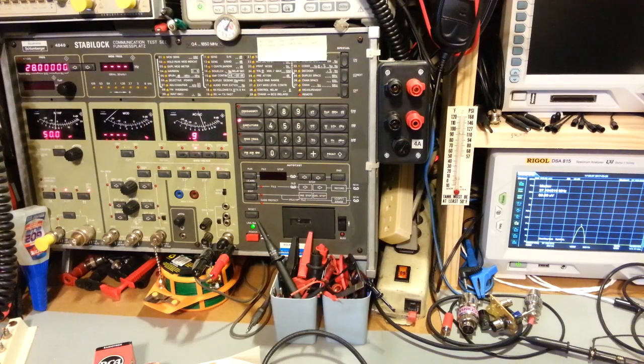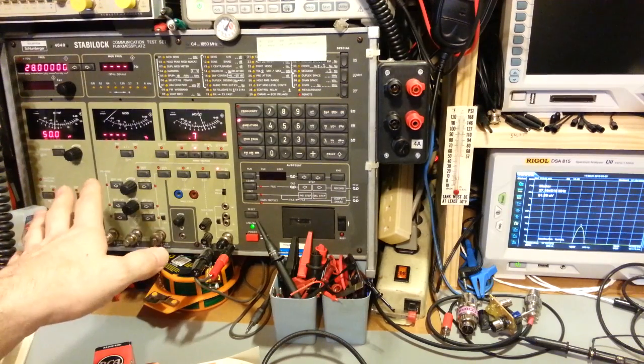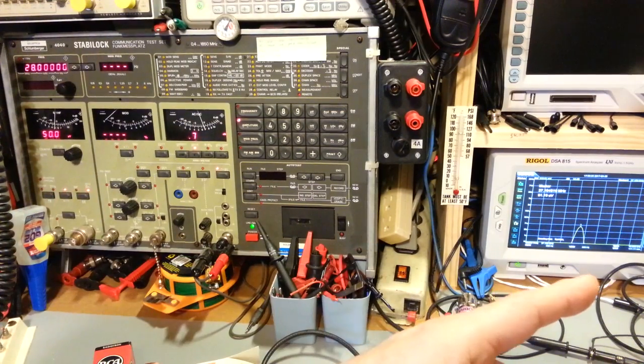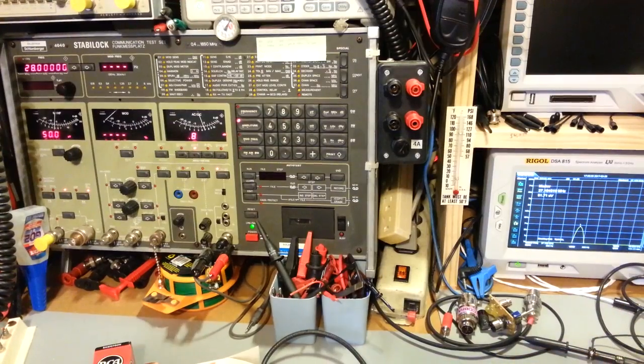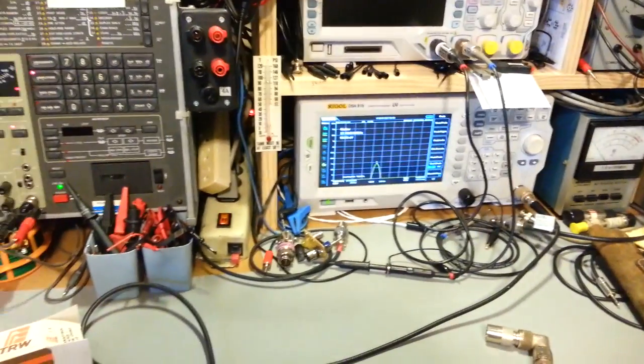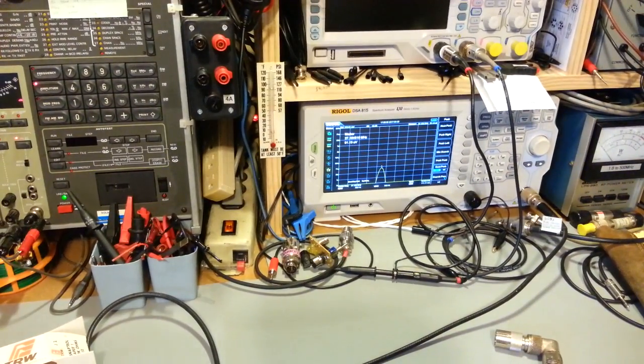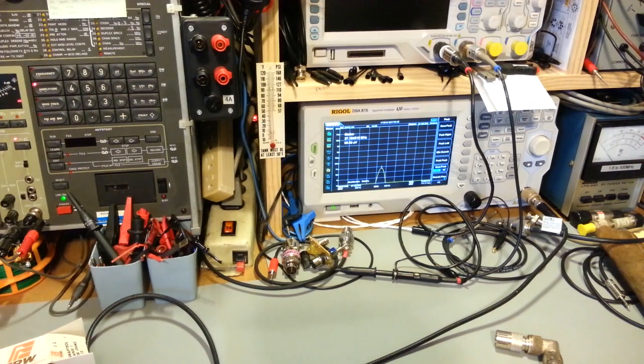So that's where it can be confusing, especially if you have more than one piece of test equipment. One might be calibrated into 50 ohms, the other one might be calibrated EMF, so just be aware of that. Now granted, it's not the end of the world if you don't get your S-meter calibration correct, but other than maybe an unhappy customer, that's just one of those things to be aware of.